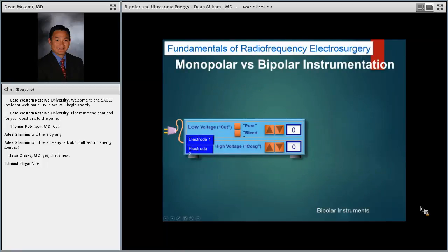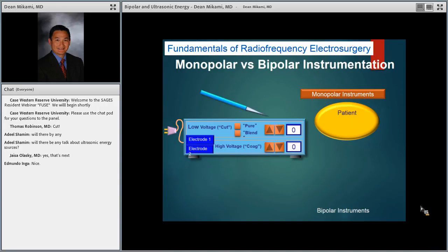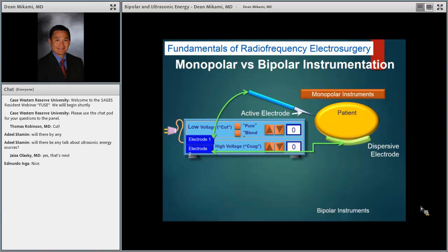Okay, so now we're going to move on to bipolar energy or bipolar RF. So what is the difference? Both of them are actually bipolar energy, because in monopolar mode, we have the active electrode. The patient is this yellow oval part, and we have the dispersive electrode, and the ESU is just trying to complete the circuit. So energy or current goes in, goes through the patient, you get your end tissue effect there, goes through the dispersive electrode back to the circuit.